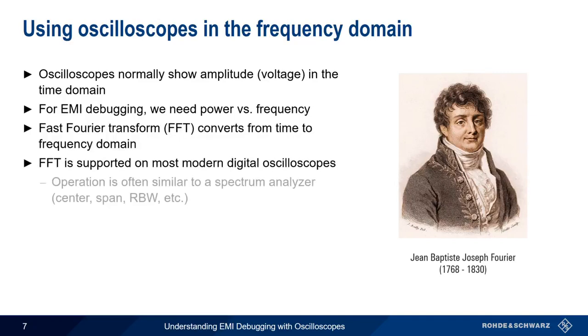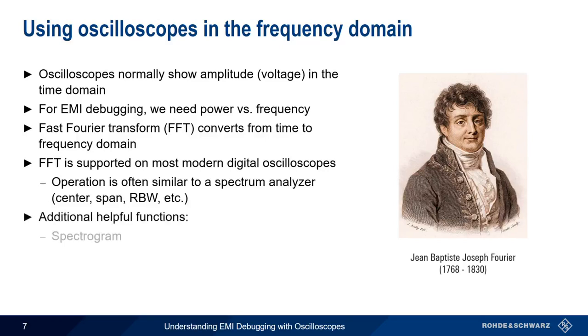FFT mode on oscilloscopes is usually very similar in operation to spectrum analyzers, for example, setting the center frequency, span, resolution bandwidth, etc. In addition to the basic FFT operations, additional helpful functions include spectrograms, frequency mask triggers, and peak lists. Let's look briefly at each of these.